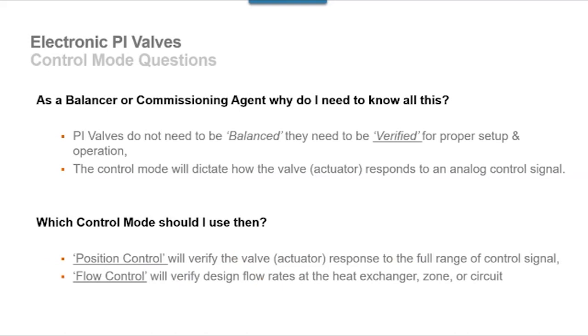So this is probably the question: why do you need to know all this? Well, it goes back to what Brian mentioned a few moments ago. PI valves don't need to be balanced. They need to be verified for proper setup and operation. More importantly, somebody should check. If you get them from the factory, they can be purchased, tagged, and preset with the proper Vmax. But we all know, with a box of 1/2-inch valves, they may or may not get put in at the right coil. So verification is proper. Depending on the consultant, verification may include specifications. Verification may include verifying you have a 5-pound differential. There can be many levels of verification.